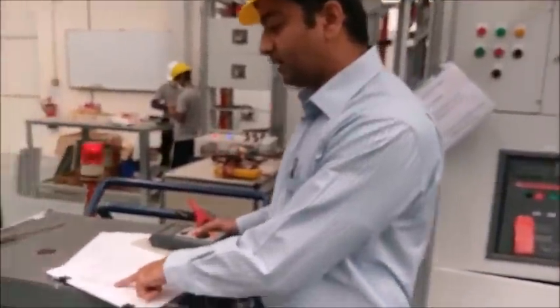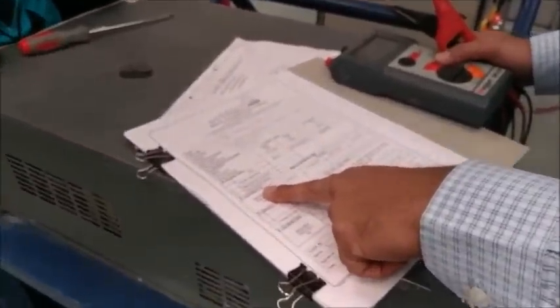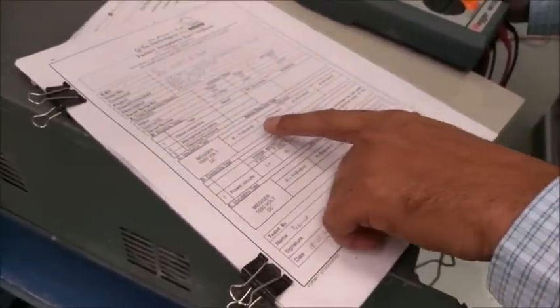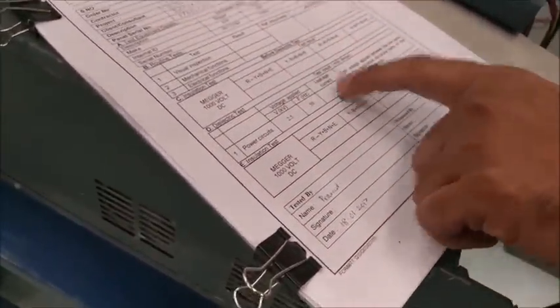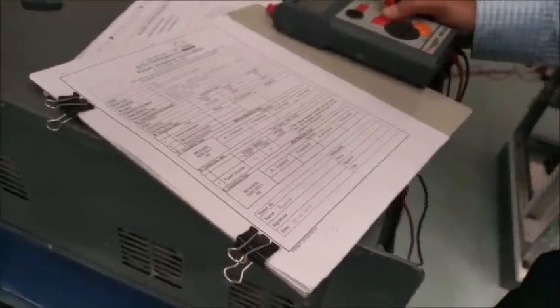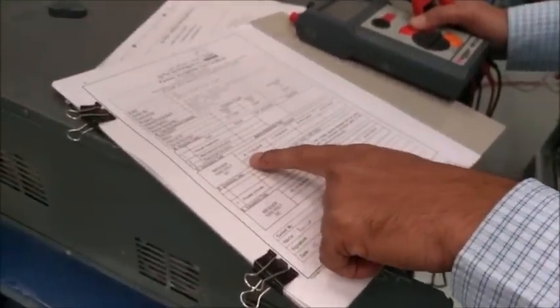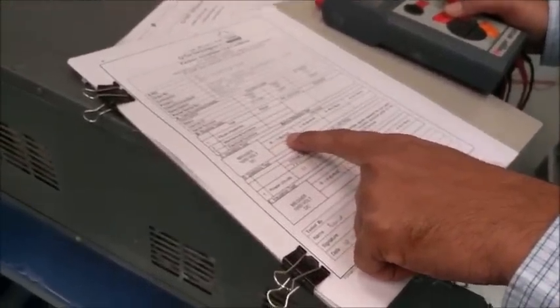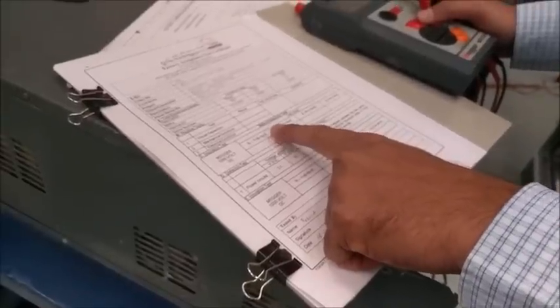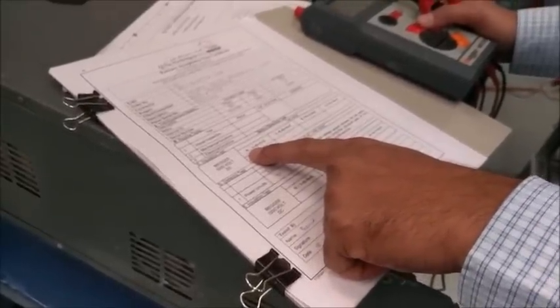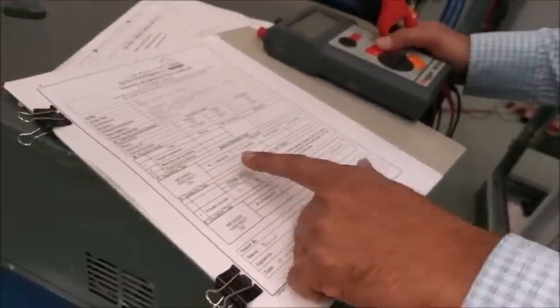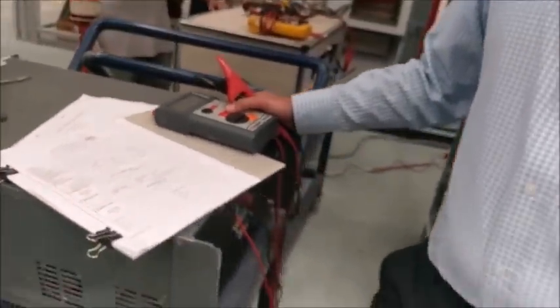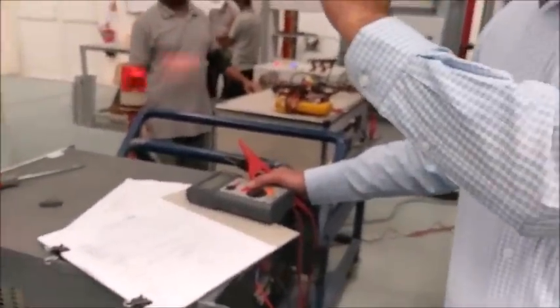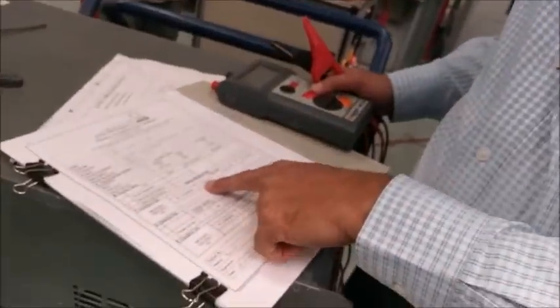Then comes the Megger, insulation test. Before the dielectric test, we have to perform Megger once. For the connections, we short Y, B, neutral and earth, and with respect to this we test the R phase. So it's the insulation between the R phase and the rest. Similarly, yellow to the others, blue to the others, and neutral to the others.